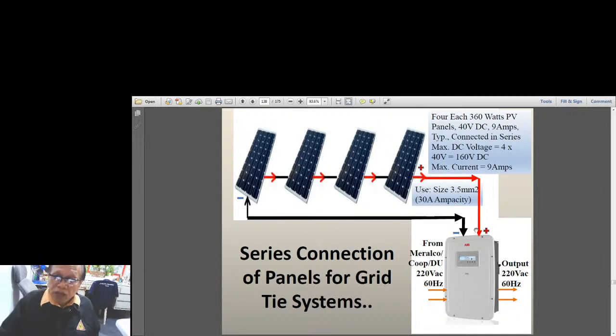Take note of the polarity, as well as you are not supposed to exceed the DC input voltage of the inverter. So if the inverter has, let's say, 180 volts, having 40 plus 40 plus 40 plus 40 would be 160. That means the input is 160. You should not exceed the maximum rating or the minimum rating of this.